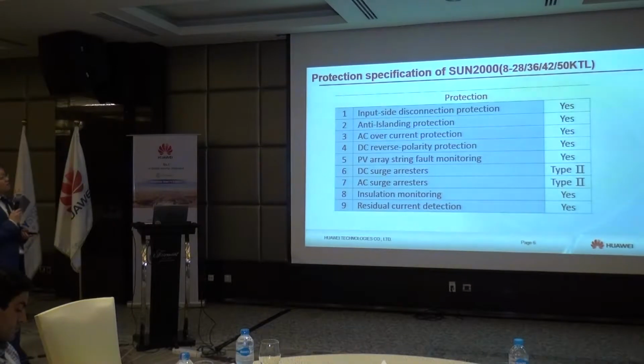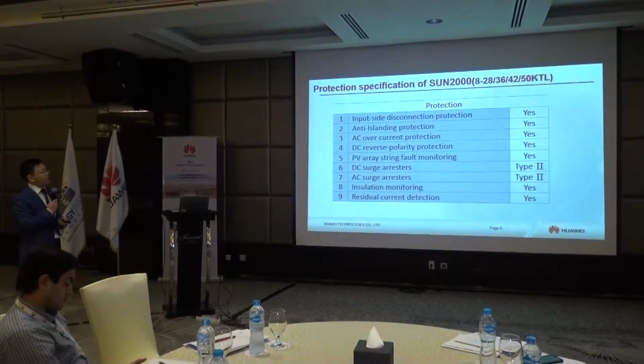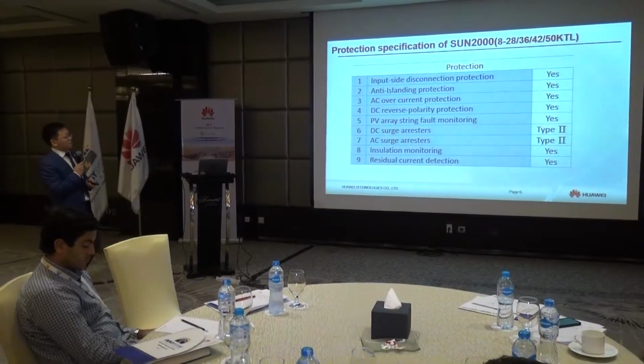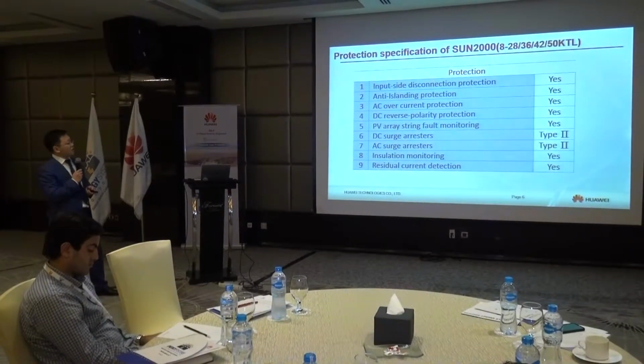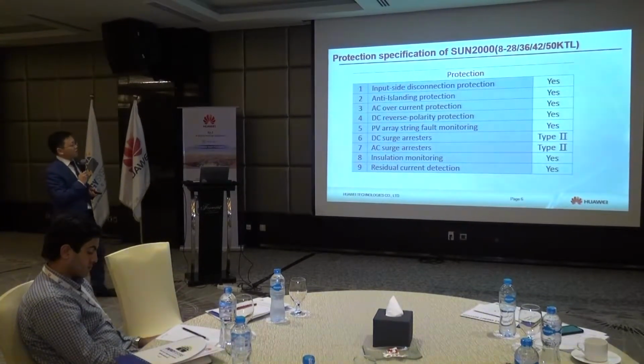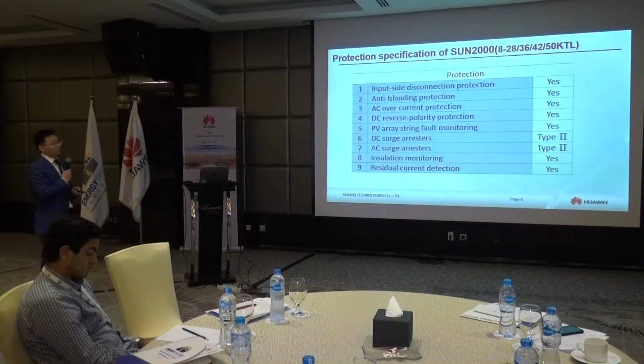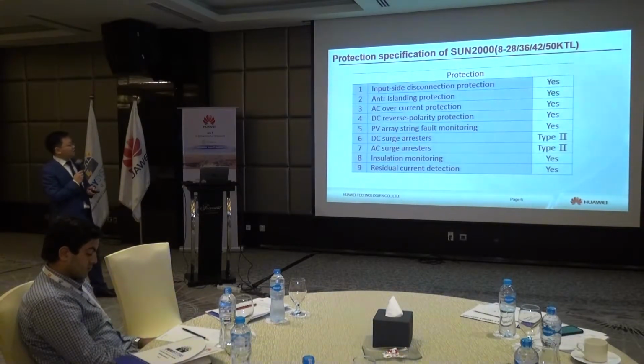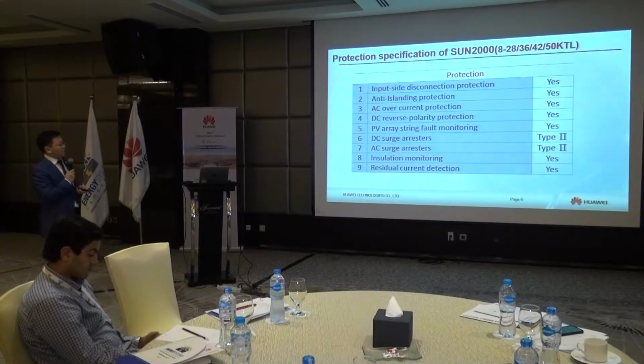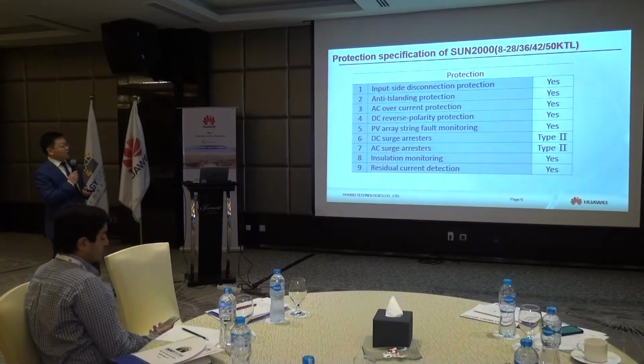As for the protections we have, for example, we have input side disconnection protection, anti-islanding protection, overcurrent, over voltage, and reverse protections, and also some other protections. As for the DC and AC surge protection, we use type 2. We can also read the insulation values before we start our operations, and we also support RCDs.